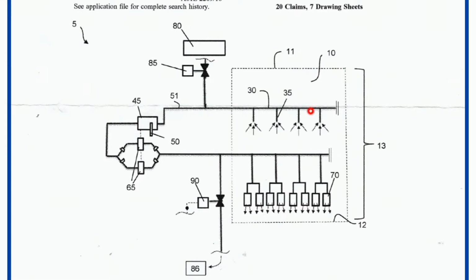The collection pipe takes the hot air into the air handler, where it's cooled and treated with UVC light. The air is then fed to 2 turbo boosters because we have to boost the pressure up to run this system. The low velocity diffusers take more pressure to run. These boosters then feed our low velocity diffusers that are in the room sitting on the floor. We have the ability to bring in fresh air from the outside, and we have the ability to purge air to the outside in the system.